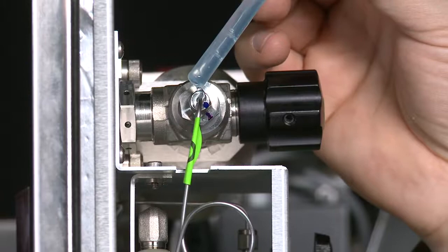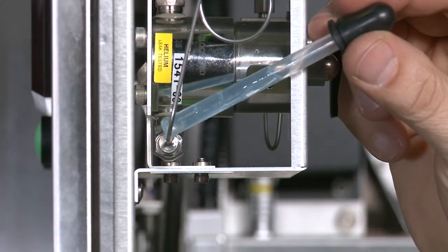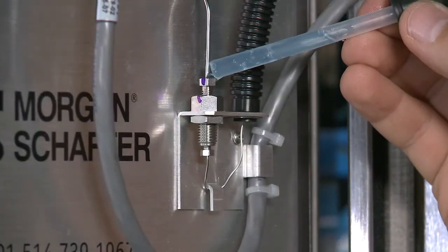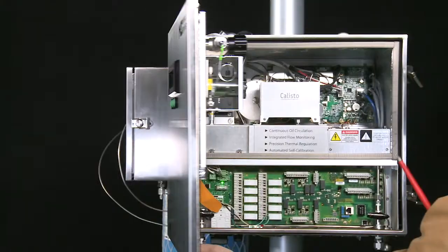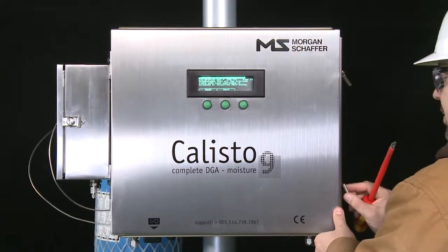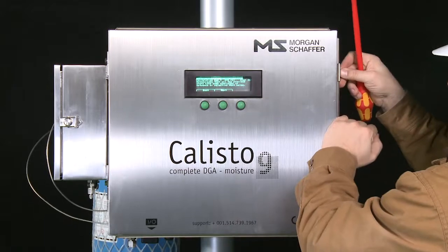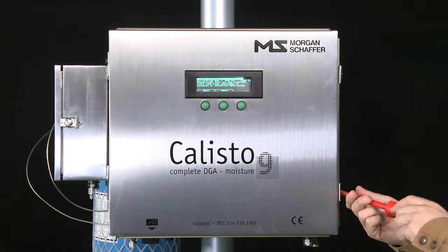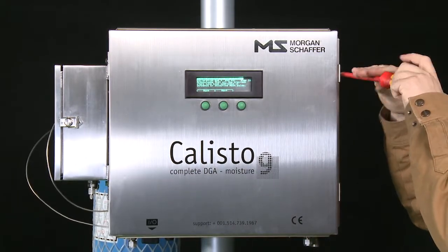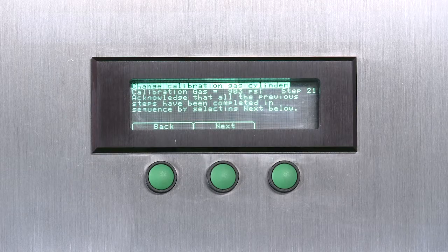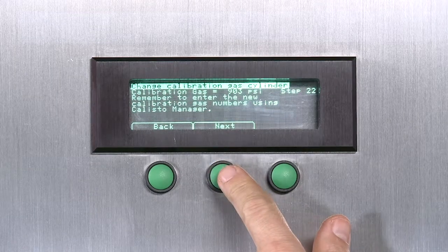Use Snoop or helium detector to check that the cylinder connection is leak-tight. Close the Calisto door. Fully tighten the door latches to prevent water ingress. Acknowledge that all the previous steps have been completed in sequence by pressing Next.